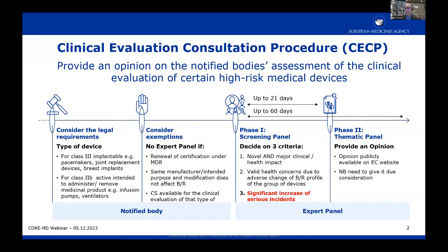And in this particular case, it applies to specific high-risk medical devices, which are class 3 implantable devices or a particular type of class 2B active devices, the ones that are intended to administer or remove medicinal products. Actually, a first part of Rule 12 of the MDR. And so for these types of devices, the expert panels provide an opinion on the notified body's assessment of the clinical evaluation that they have provided during the conformity assessment of those medical devices.